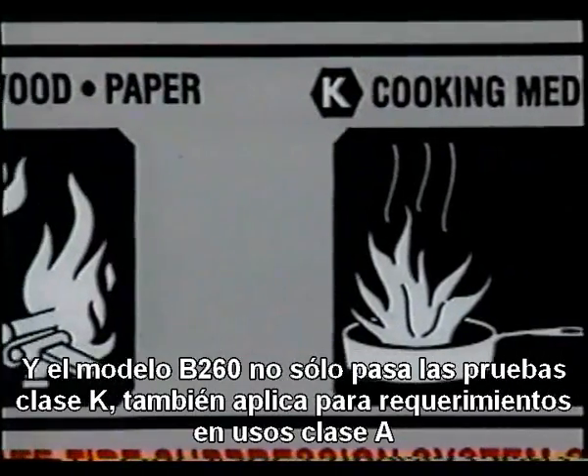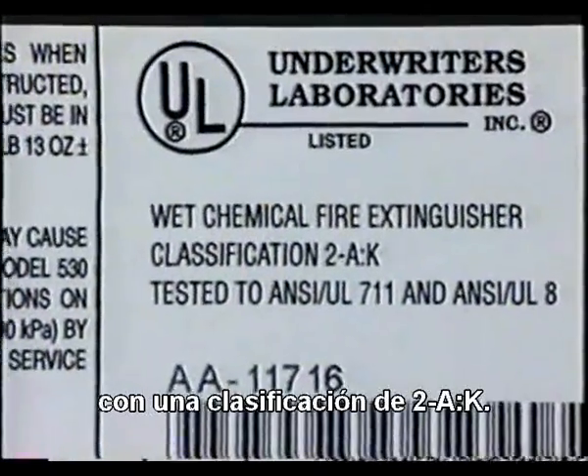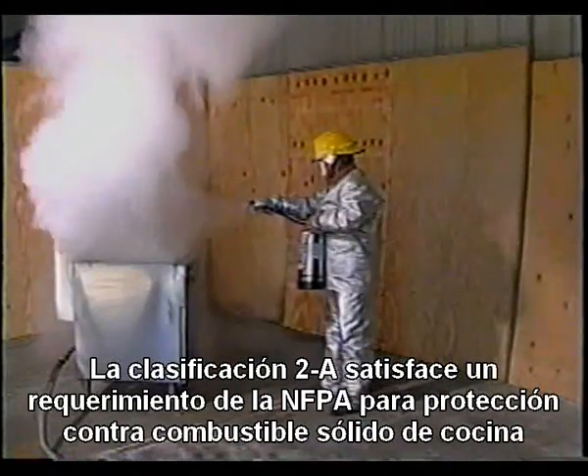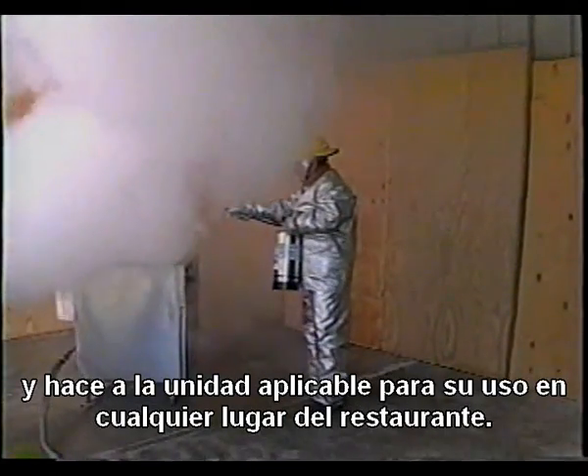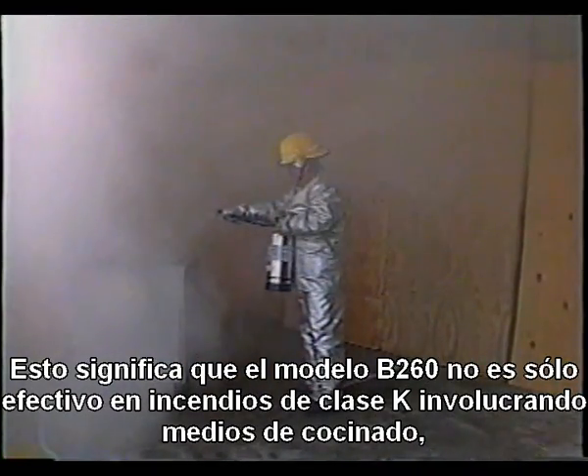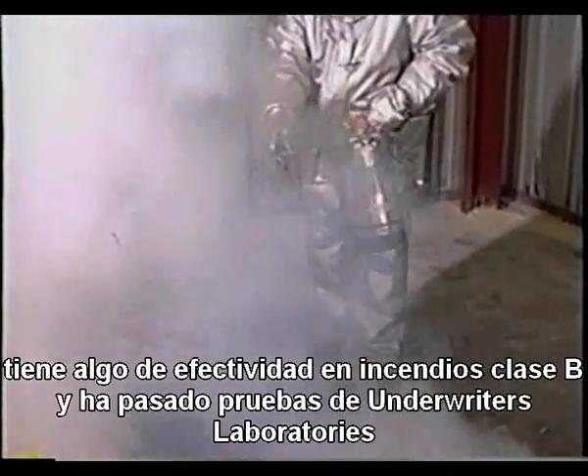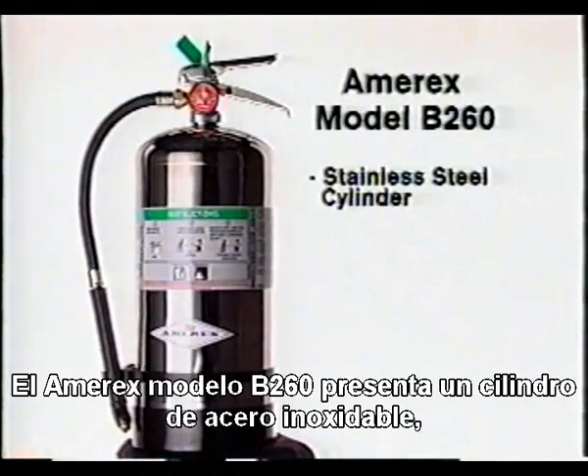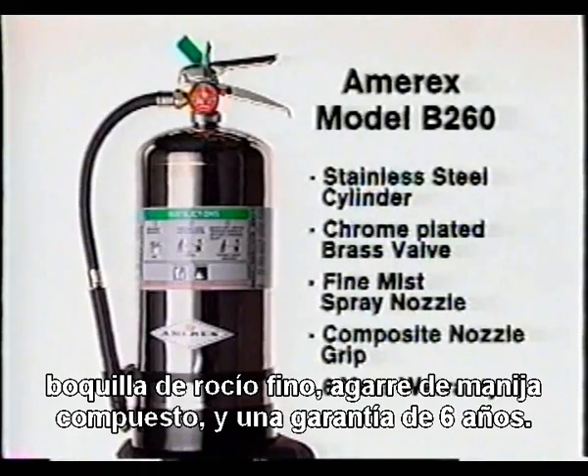Not only has the model B260 passed UL's Class K testing, it also qualifies for Class A requirements with a rating of 2A-K. The 2A rating meets NFPA's requirement for protection of solid fuel cooking and makes the unit applicable for use anywhere in the restaurant. This means the model B260 is not only effective on Class K fires involved in cooking media, but it is also just as effective as a 2.5-gallon water extinguisher on Class A fires, has some effectiveness on Class B fires, and has passed UL's test for Class C rating. The Amerex model B260 features a stainless steel cylinder, chrome-plated brass valve, fine mist spray nozzle, a composite nozzle grip, and a six-year warranty.